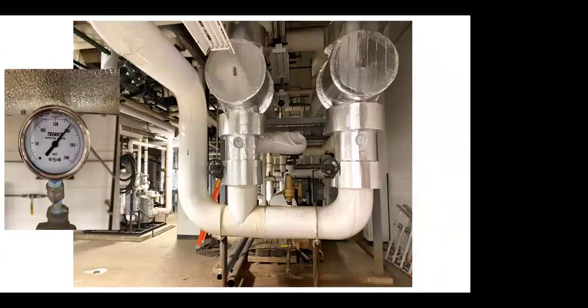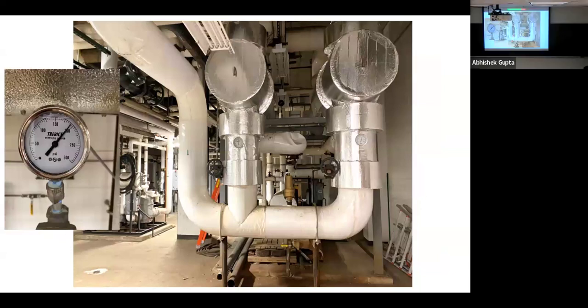Now this is an example - I'm going to go through some examples before we talk about securing the system, just so you get an idea of what we're looking at. This is a high-pressure steam station over at Scott Lab. You can see the gauge reading 200 PSI, so we have very high-pressure steam on campus. We're slowly converting that over to hot water systems because it's less dangerous, causes less wear and tear, and is more efficient. This is 600-degree heat - superheated steam, we call it.